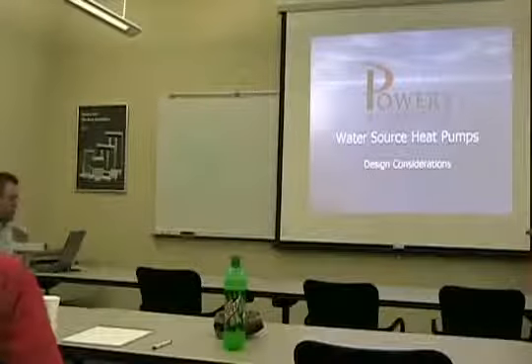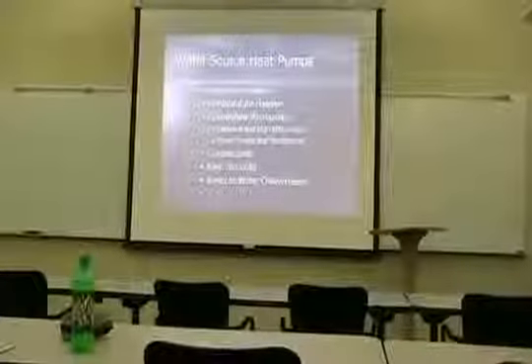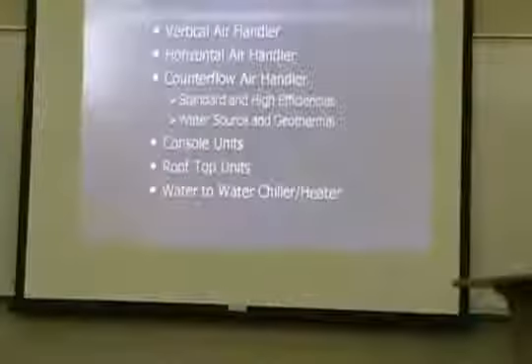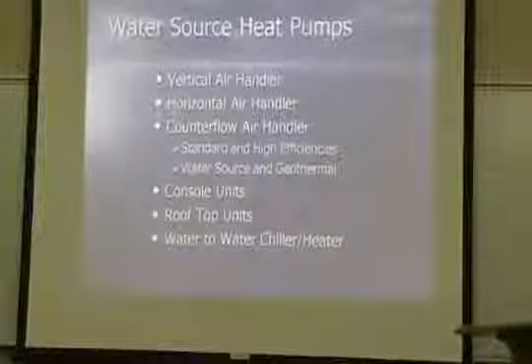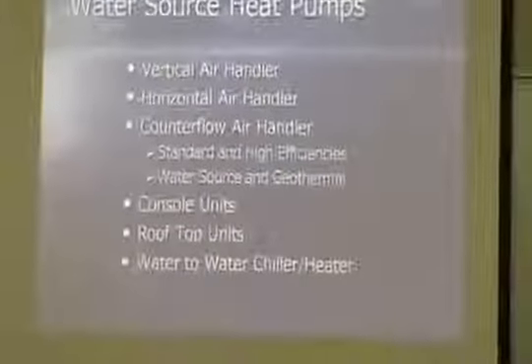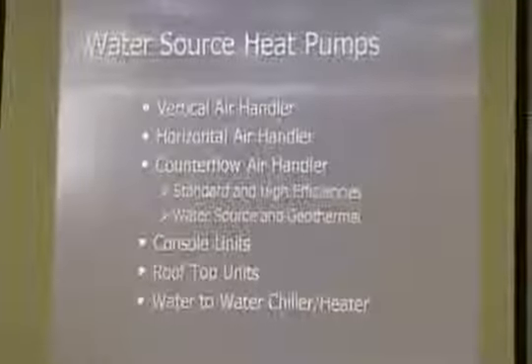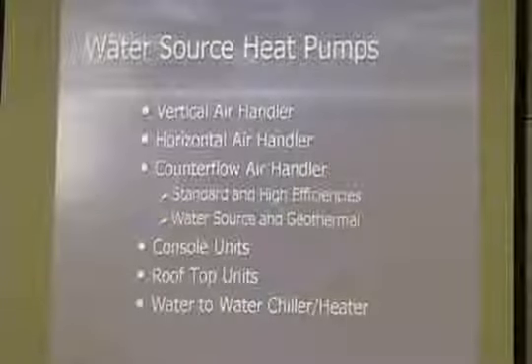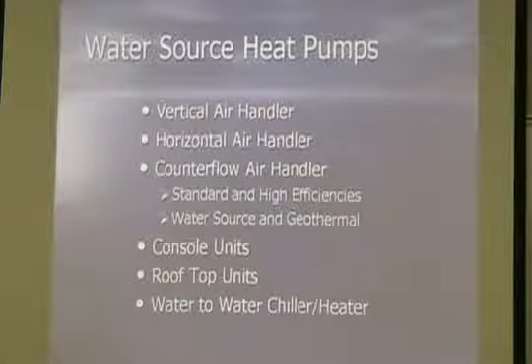Start with talking about water source heat pumps. A water source heat pump is a unitary type piece of equipment. It's packaged: compressor, fan, evaporator, condenser. They're water cooled compressors, hence water source heat pumps. They're reverse cycle. In fact, I don't have that diagram drawn 100% correct.